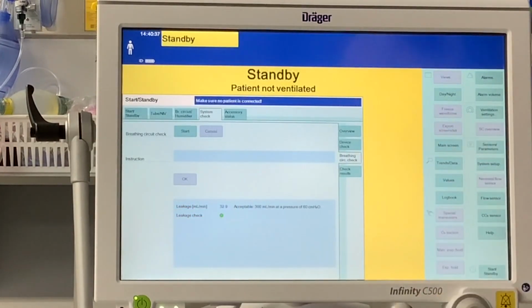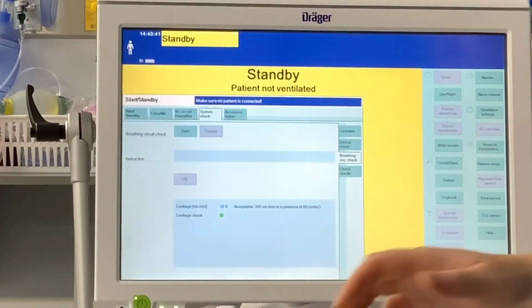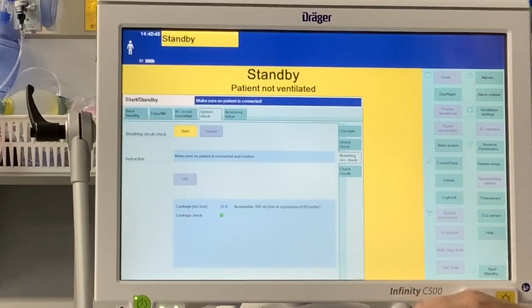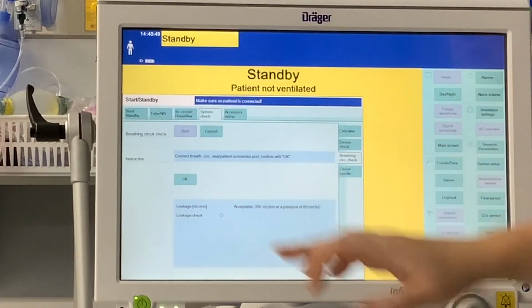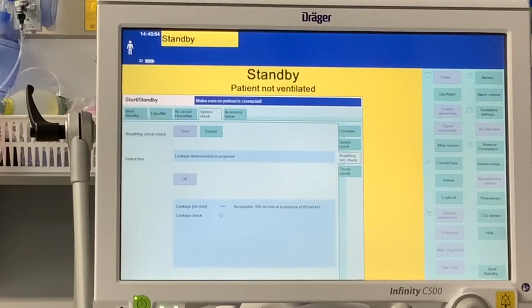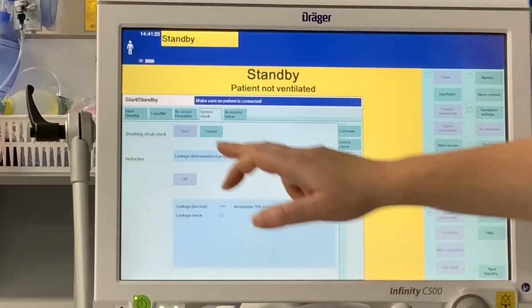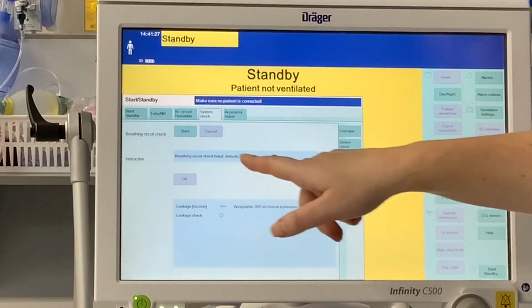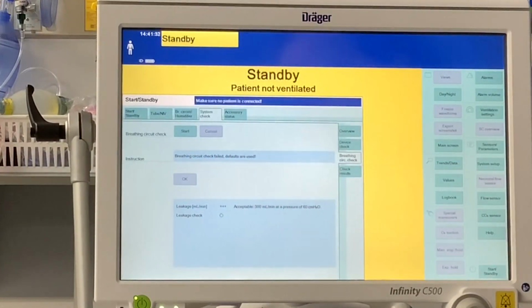I've taken that off. And then when we went through here to start, make sure no patient's connected. Seal it. When we do our leak check, it's going to say plus, plus, plus. That means we have a big leak somewhere and it's not going to pass. This is a good way to troubleshoot if there's a leak somewhere in your circuit. It won't tell you about a leak on your patient side, like in the ET tube with the cuff, anything like that, but it will tell you if you have a leak in your circuit. So I'm just going to cancel this because we know it's not going to pass. And it's going to tell us it failed. So defaults are used. Before I put this ventilator away, I'm just going to redo the breathing circuit check.